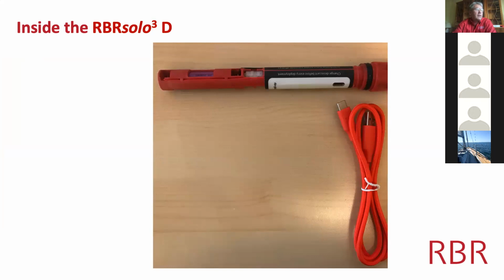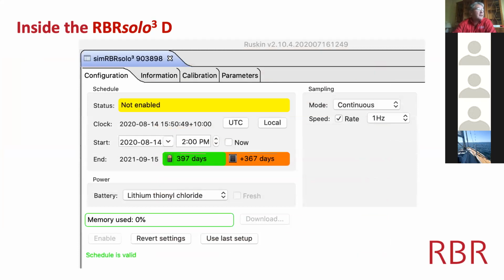And after we have a software, it's coming, it's Ruskin. And for that, you have a connection directly with a software display, and you have the possibility to check the configuration of the system, to change the sampling rate and schedule your time deployment, the date of the start, and you have the possibility to have the end of the deployment too, on the choice of the battery. I will show you that just after.